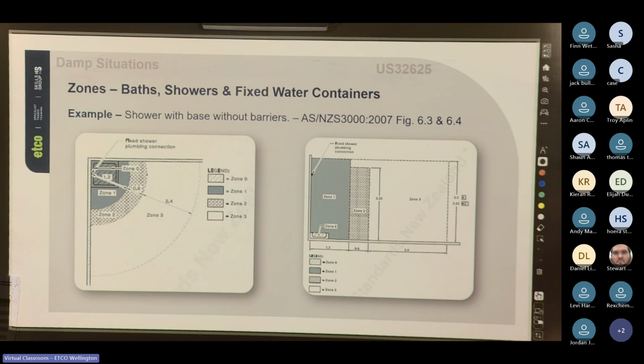so this is figure 6.3 and 6.4. So this is a shower with base without barriers, so an open shower. So we have zone 0 is pretty small because it is just the water container. But if you notice, zone 1 extends out 1.2 meters from the fixed shower plumbing connection. So basically 1.2 meters from the shower head. Does that make sense?